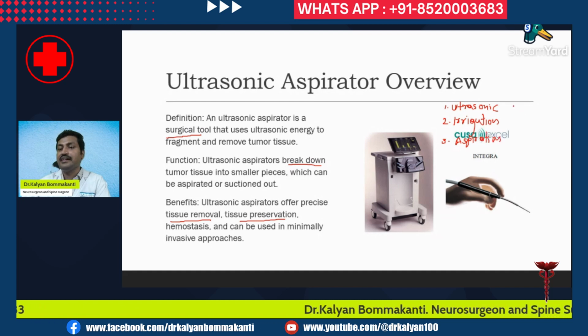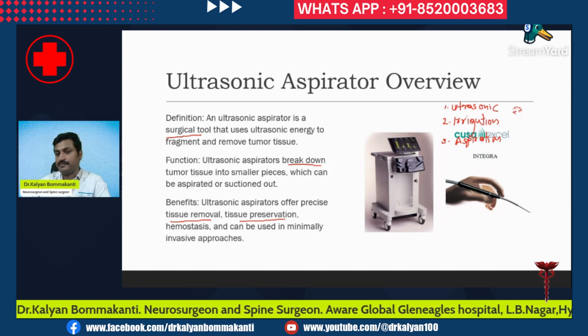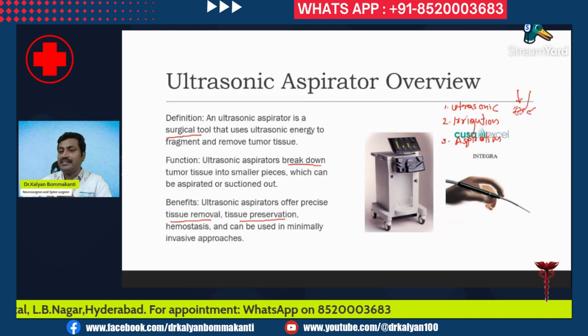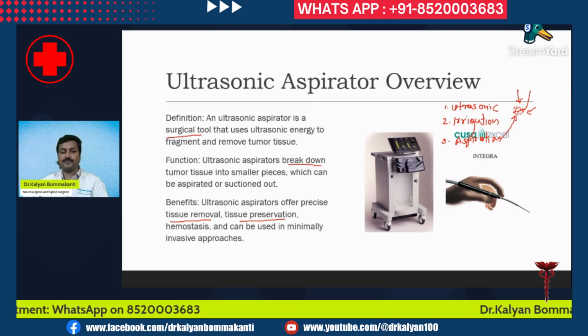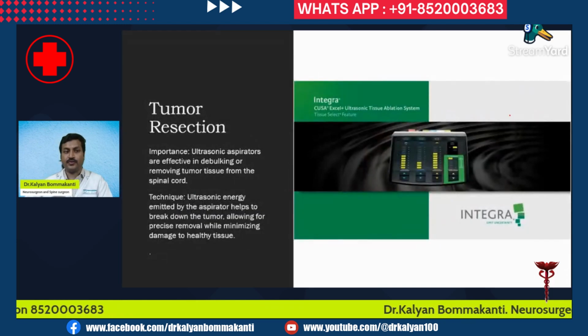How does this happen? The ultrasonic portion breaks the tumor tissue into smaller pieces. The irrigation channel continuously pours water into it, so that this forms an easily suckable tissue, and the aspirator sucks that tissue.